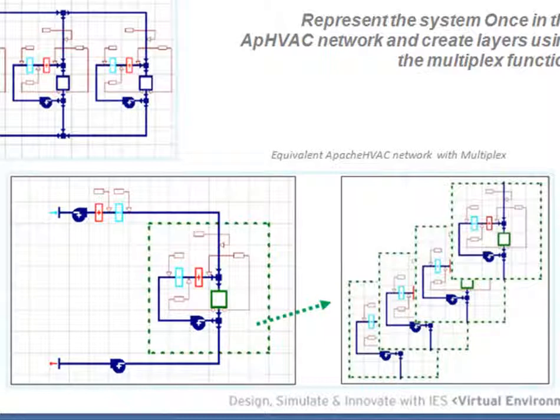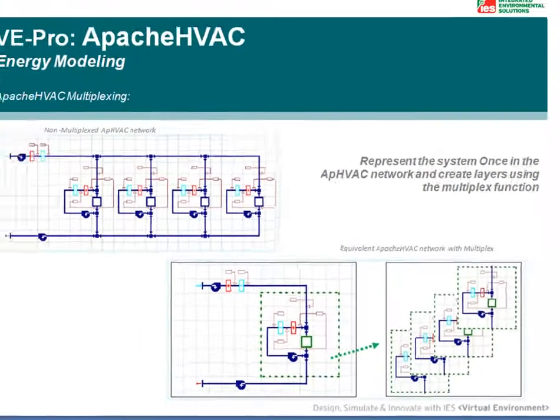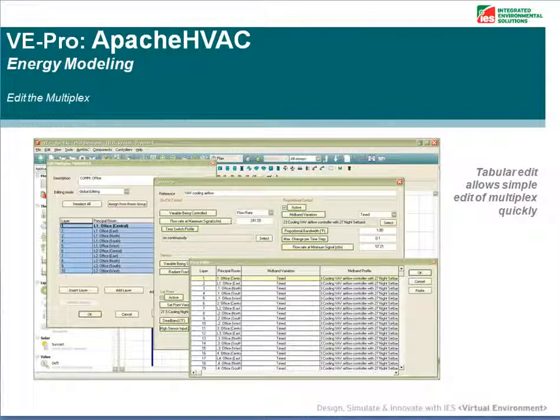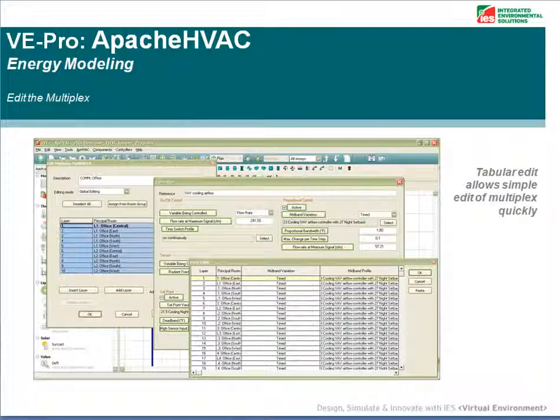This fan coil unit can then be multiplexed. When a multiplex is created the system can be layered so that there are multiple layers — four in this case — representing each of the four zones and systems. You can easily edit the inputs for the layers in your multiplex using the tabular edit function, which allows you to select multiple layers and variables to edit at one time. You can also copy and paste the inputs directly from Excel.